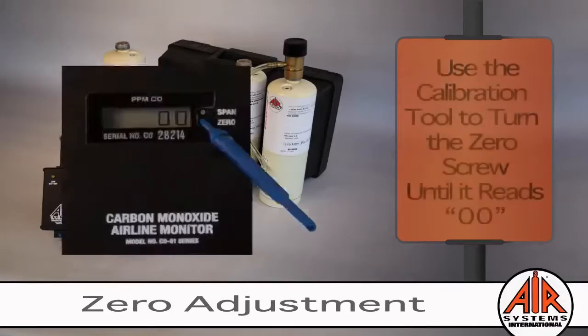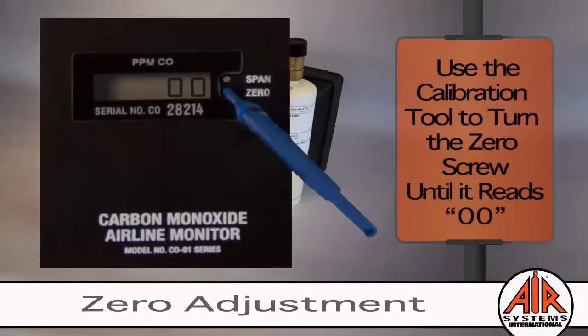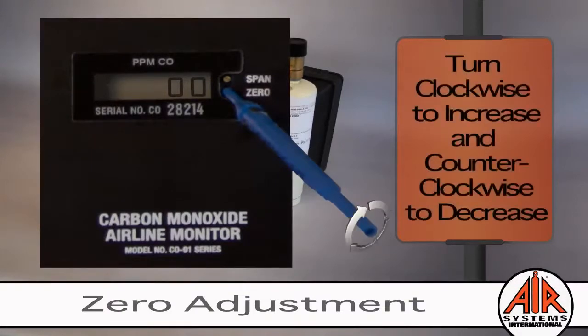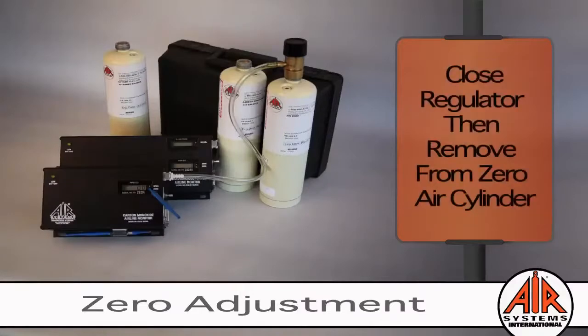Use the calibration tool to turn the zero screw until it reads a value of 00. This is achieved by turning clockwise to increase the value and counterclockwise to decrease the value. Close the regulator, then remove from the zero air cylinder.